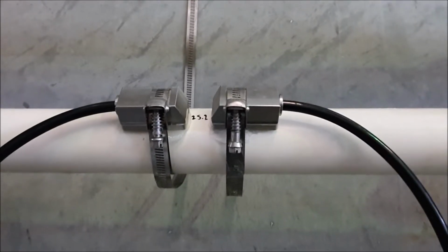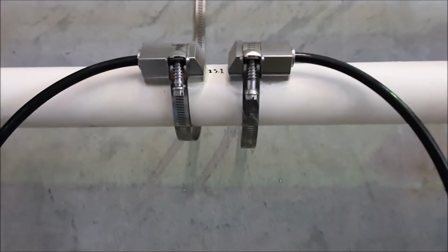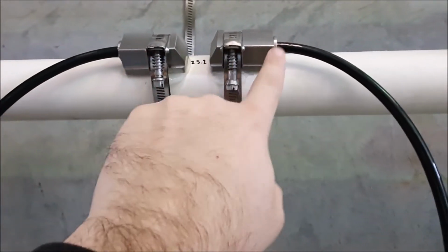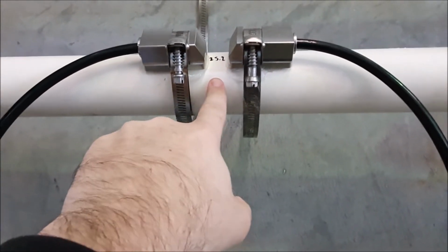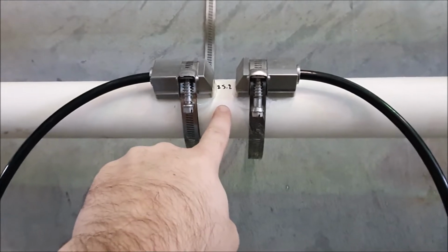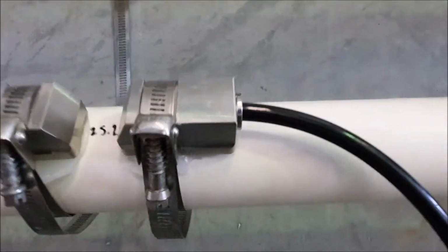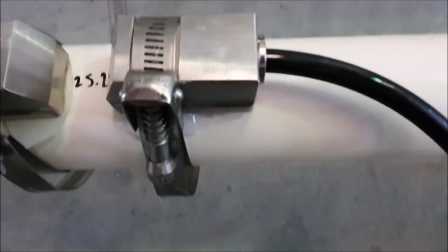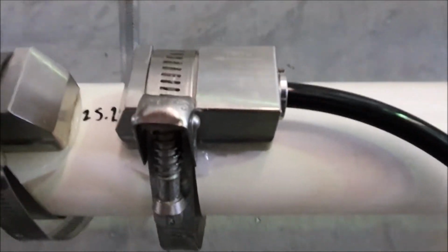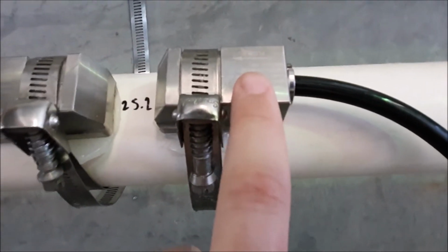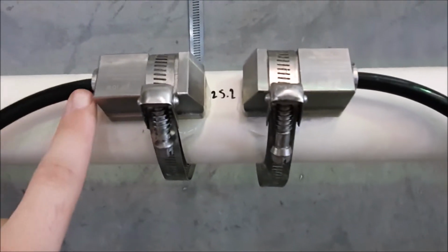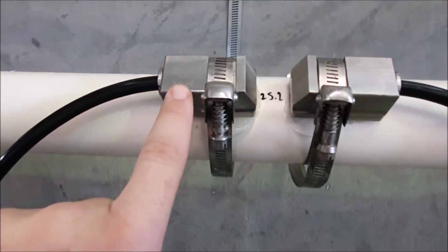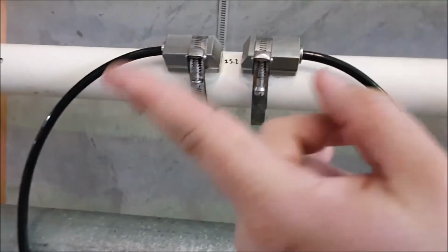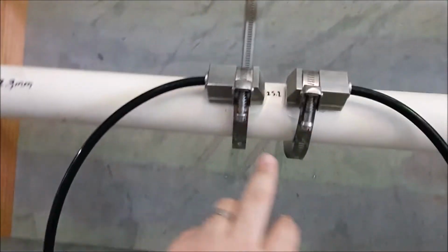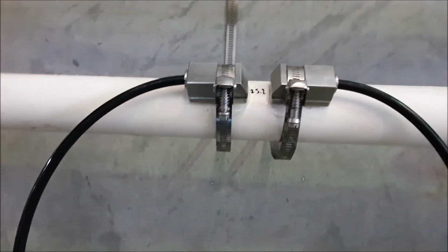Okay, so you can see I've got the transducers mounted up now. So we have both transducers in place, they're spaced correctly as per menu 25. The other thing you'll notice on the transducer itself, it's going to be hard to see in this light to get it on just the right angle, but it does have an arrow. This shows the flow direction, so just make sure you've got them mounted in the correct position. In this case, the flow is going in this direction, so the arrows are pointing that way.